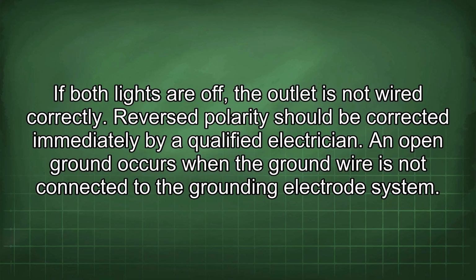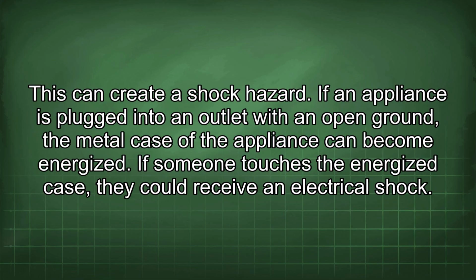If both lights are off, the outlet is not wired correctly. Reverse polarity should be corrected immediately by a qualified electrician. An open ground occurs when the ground wire is not connected to the grounding electrode system. This can create a shock hazard.